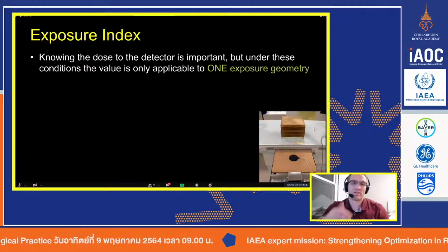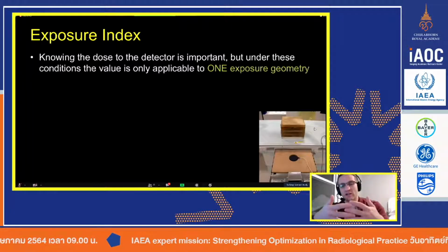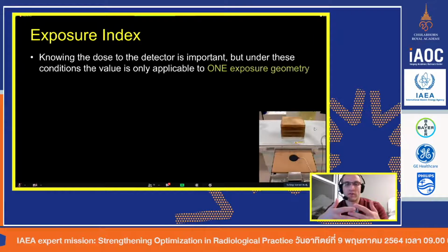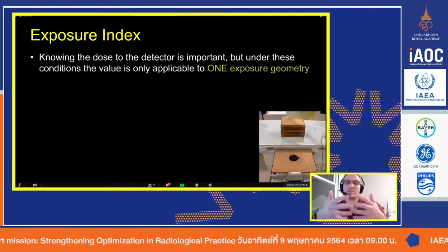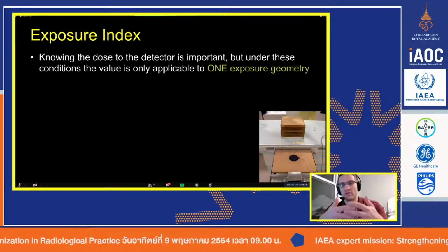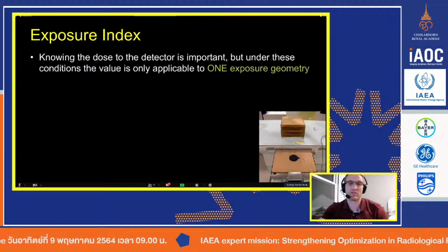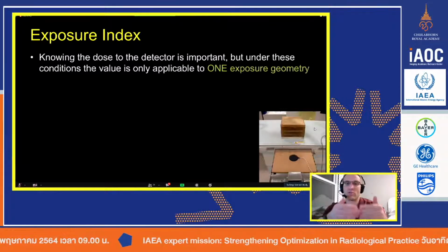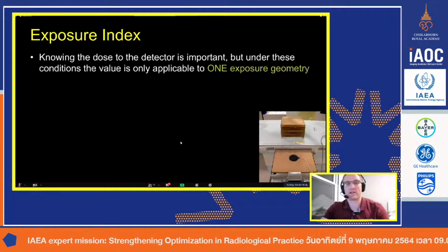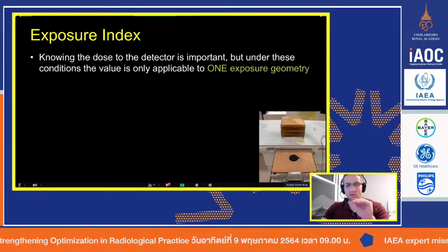Now, if you've not set that up, and I've seen this where you go in and you just check the calibration and you look at the dose to the detector and it might be 4, 5, 6 microgray. It's just way, way high. That means for those systems that are imaging patients, they will get 2, maybe 3 times the amount of radiation dose as another system that's properly calibrated at 2.5 microgray. So it's very important to have that properly set up, because the automatic exposure system is based almost exclusively on that number.